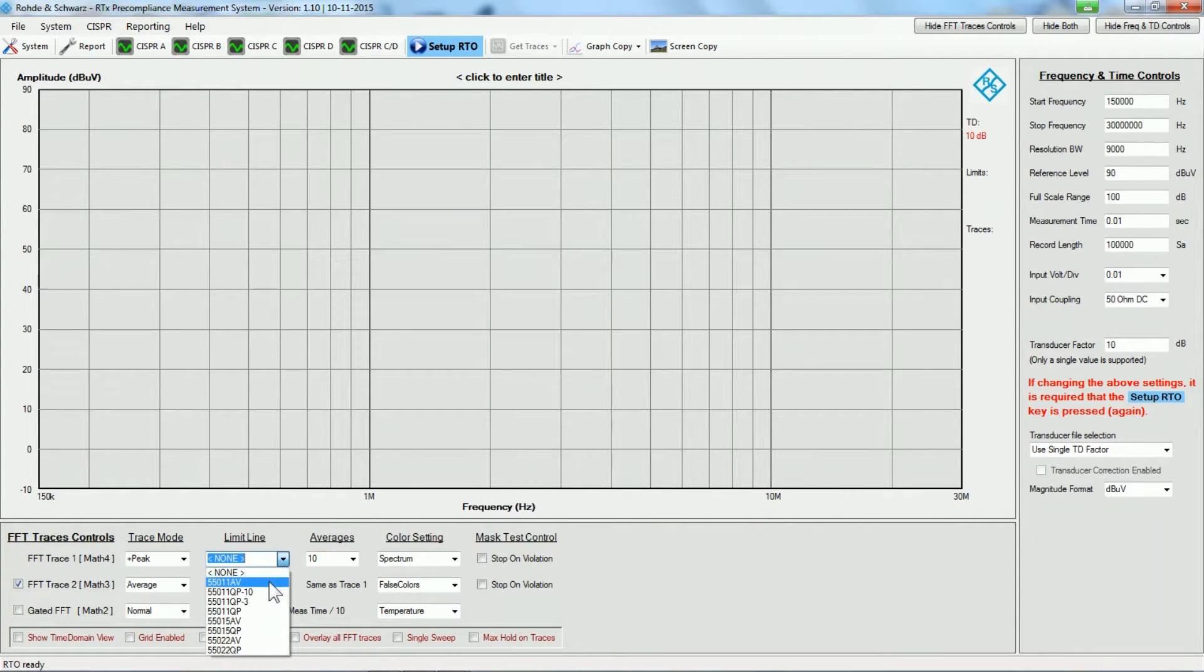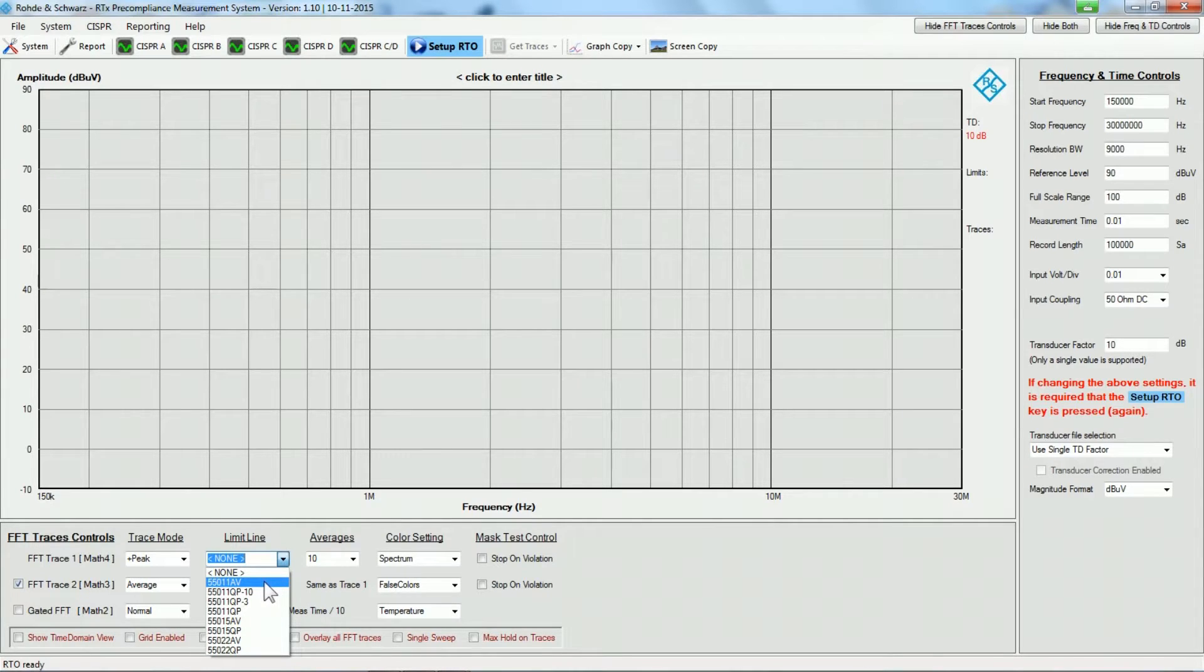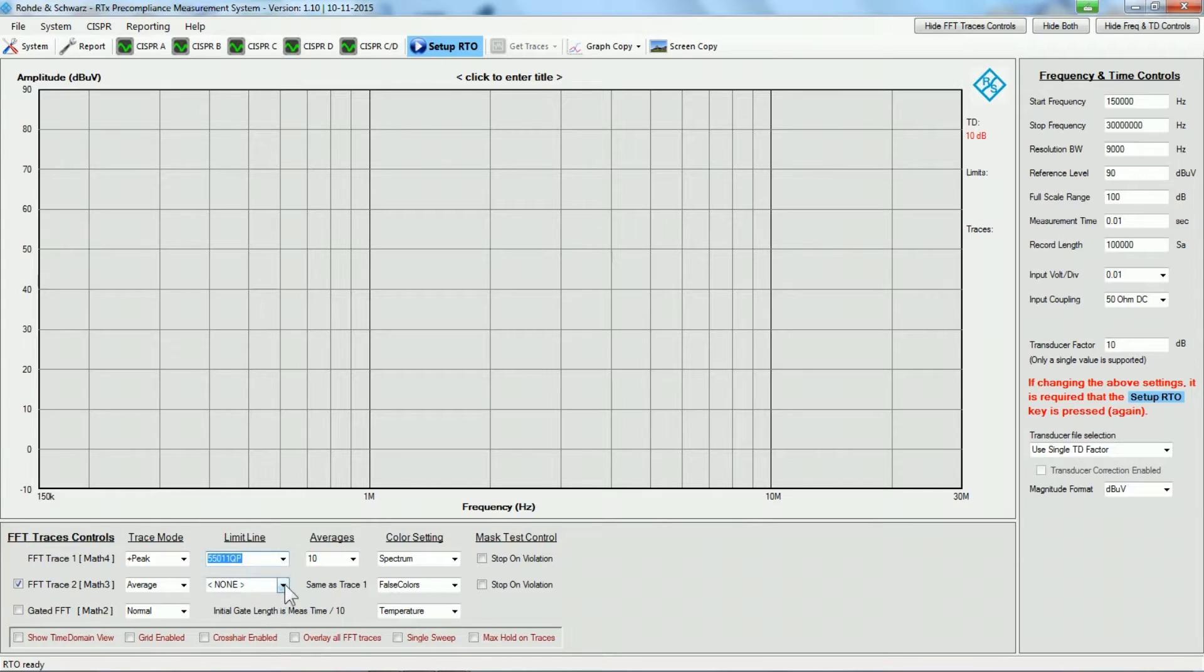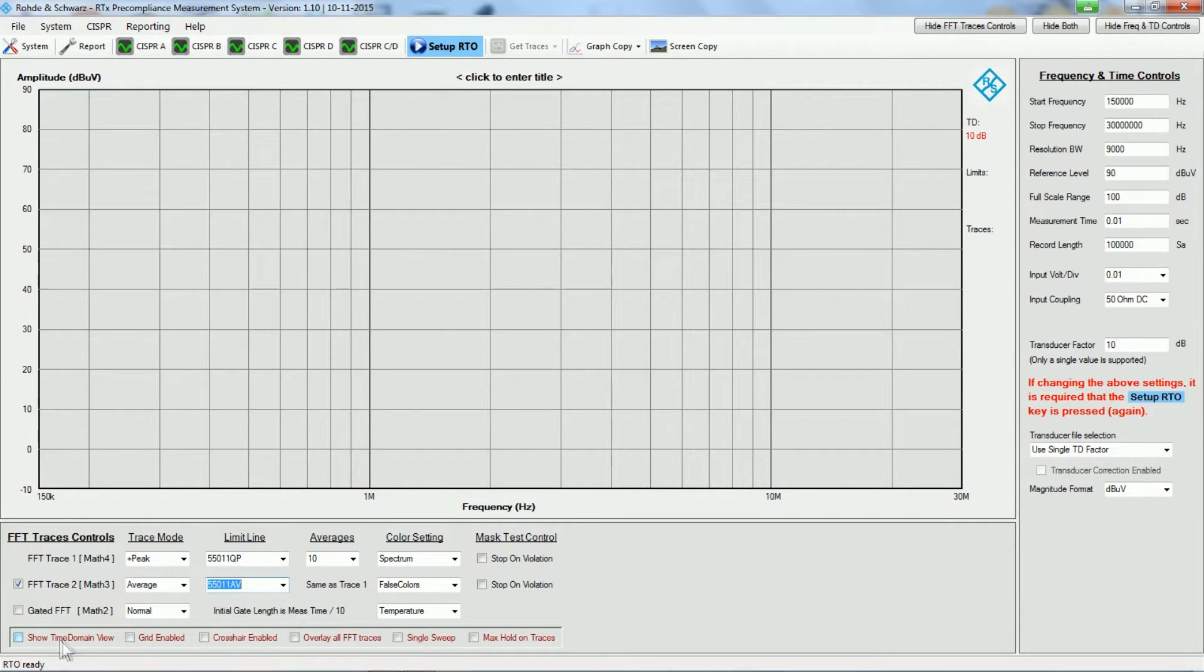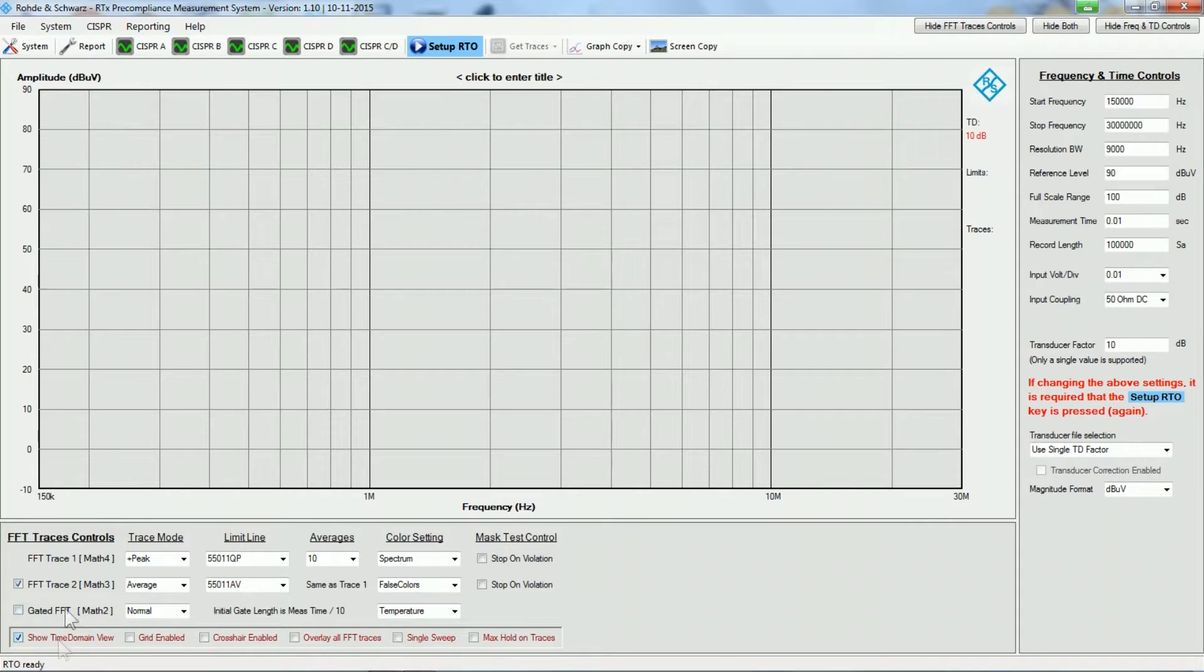We will set up of course a peak limit line for the peak detector and an average limit line for the average detector. I would like to see the time signal on the scope as well, so I am putting a check mark here, and that is basically it.